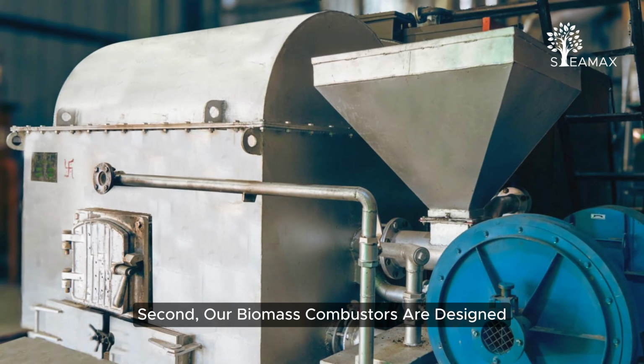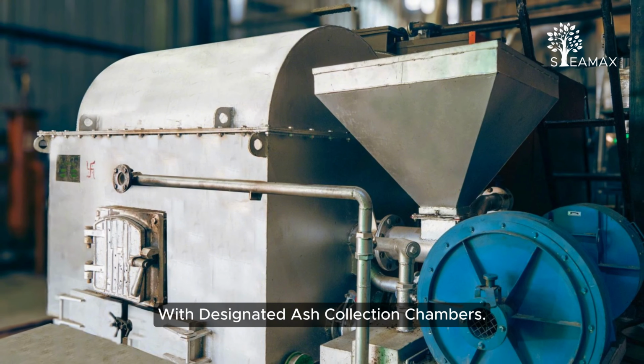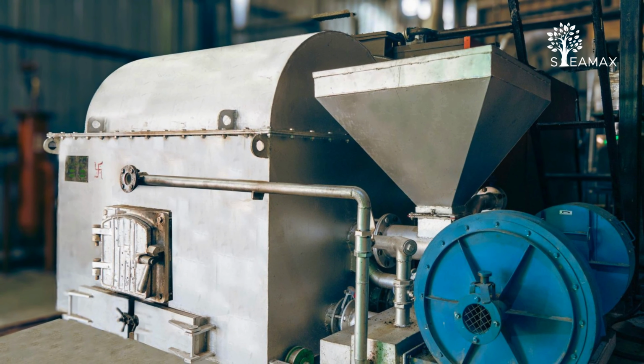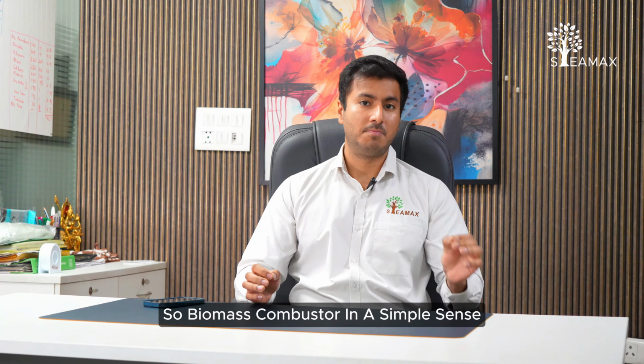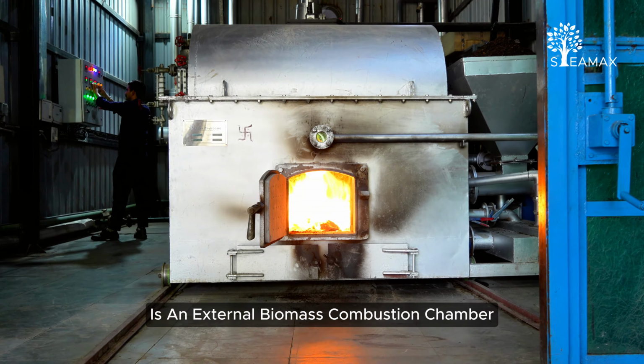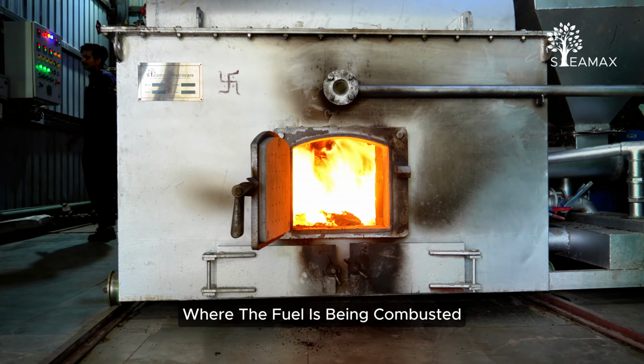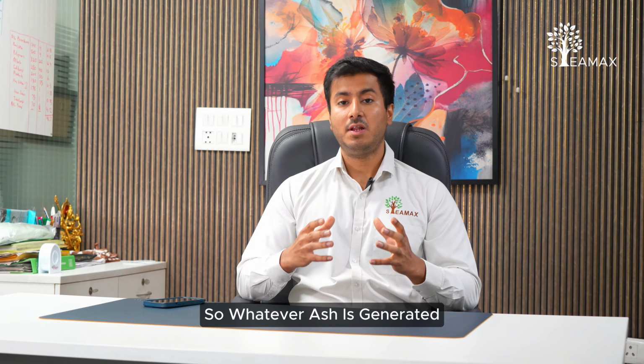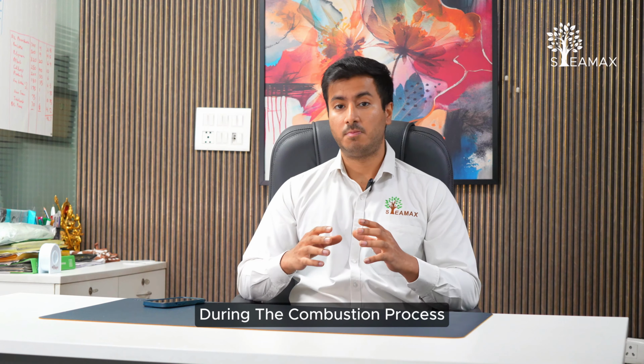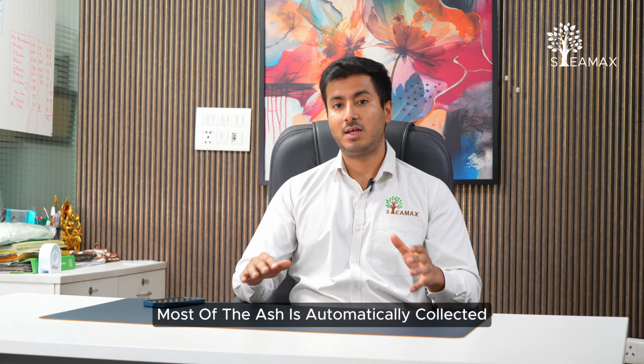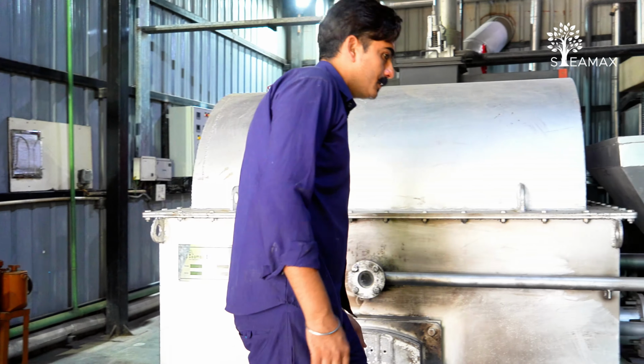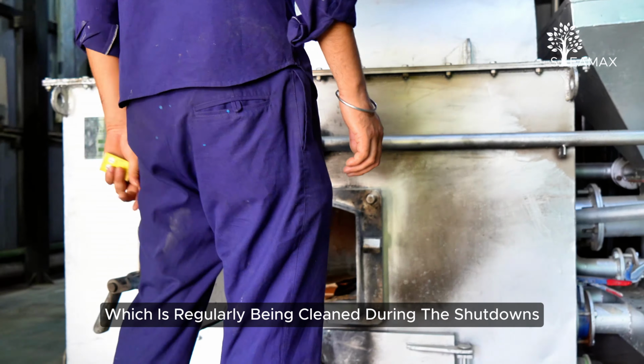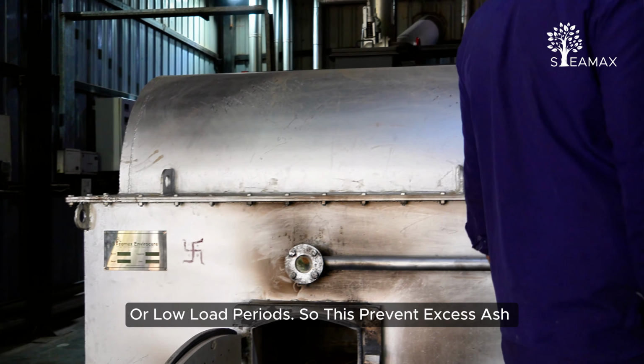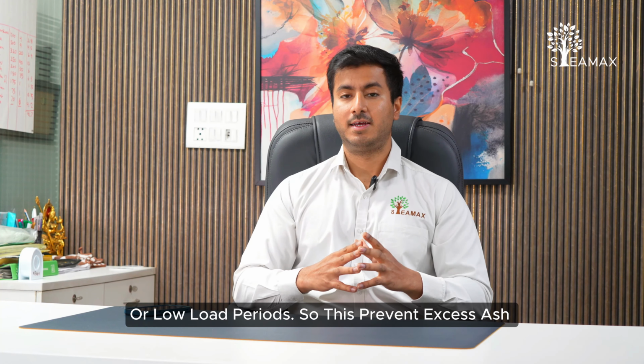Second, our biomass combustors are designed with designated ash collection chambers. A biomass combustor, in a simple sense, is an external biomass combustion chamber where the fuel is combusted. So, whatever ash is generated during the combustion process, most of it is automatically collected inside the ash collection chambers, which are regularly cleaned during shutdowns or low load periods. This prevents excess ash from entering the boiler.